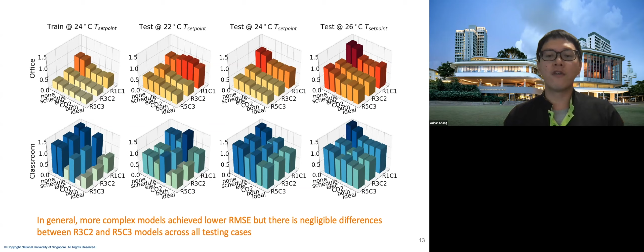In contrast, for the classroom, the root mean square error was overall larger, generally exceeding 1 degree Celsius, which is quite a big margin even for the more complex models. We also observe that including plug load data, or both plug load and CO2 data, led to better predictive performance across all models. What is interesting is that for the ideal measurement case in the classroom, we actually observe a slightly higher root mean square error compared to using other data streams.